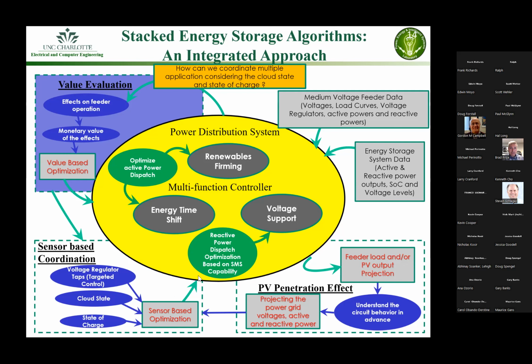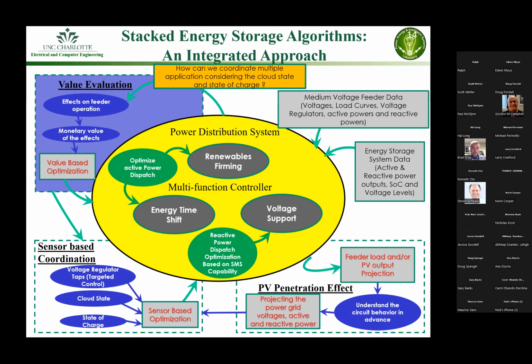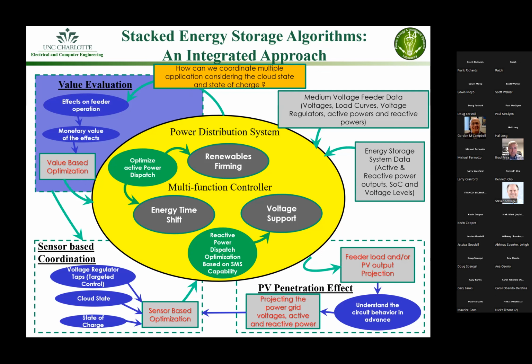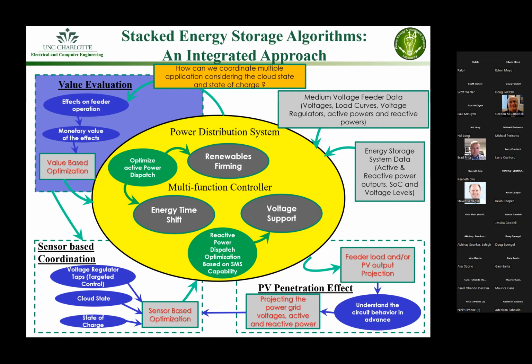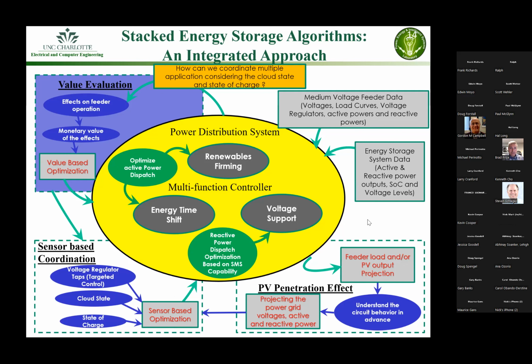These are the main three functions that we have implemented in the field. One requirement in the field implementation was to not use a lot of forecasting techniques, but utilize measurements. So the data collected from the medium voltage feeder includes voltages at the point of measurement, historic load curves, voltage regulator meter points, active and reactive power, as well as energy storage system data including reactive power, state of charge, and voltage level.